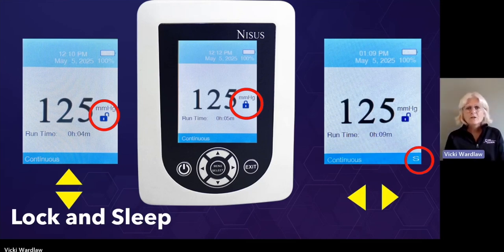So if your patient is away from their charging cord and they're getting a critical battery alarm, this will dim that LED light that sits behind that screen, and it will save some battery. To do this, you press the left and right arrows simultaneously. That S will show up indicating it's in sleep mode, and then the light will dim. If you get alarms while it is in lock or sleep mode, the alarms will bypass both of these modes. They will still show up and give you the troubleshooting to manage those particular alarms.